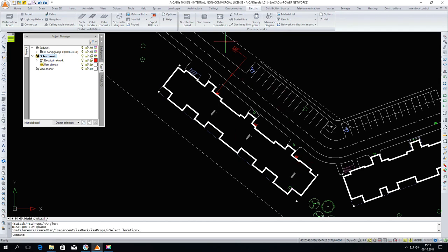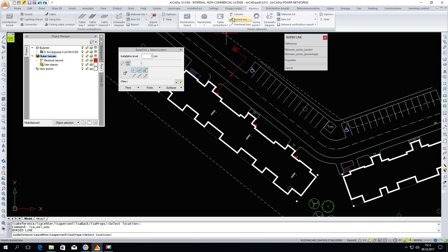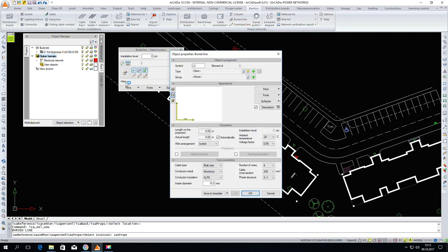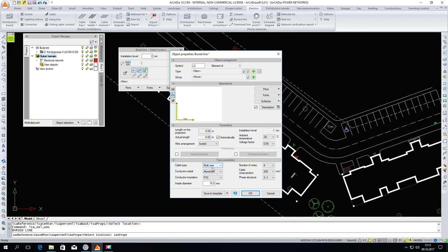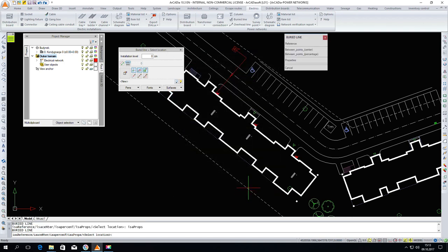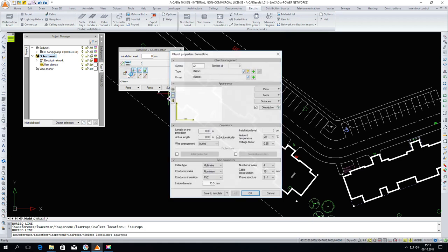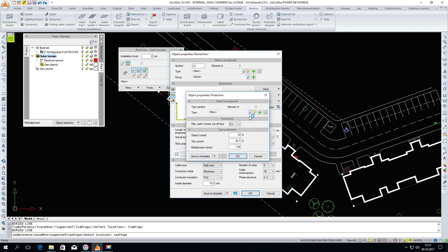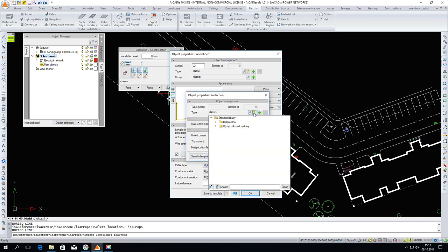The next step will be the connection of cable connectors and switchboards. I choose the buried cable and go into the properties. I will change the installation material, multi-conductor cable. Maybe it could also be a cross-section. I will leave the remaining properties. OK. We will insert a protection here. As before, you choose from the type library and insert it into our projects. OK. And we connect the buried line to our boards.